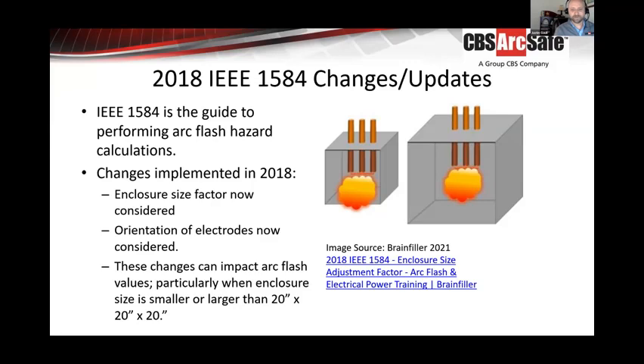We now see greater incident energy on select breakers that we didn't beforehand know were that. And so we need new solutions or devices to get us outside the arc flash hazard boundary. A lot of our customers use that 40-calorie mark as the standard for when they use remote racking and switching. We typically see that on mains, as well as places like fire pump panels and locations in the system that are fed by the outside utility without much upstream overcurrent protection.